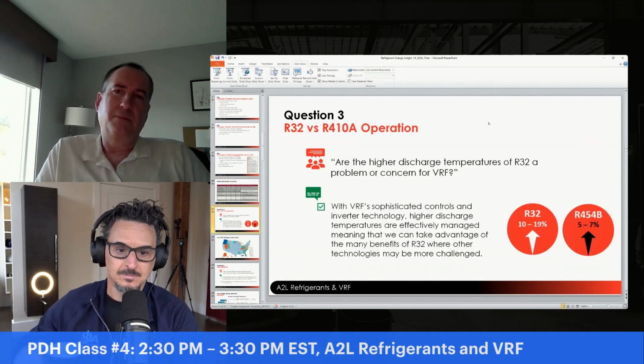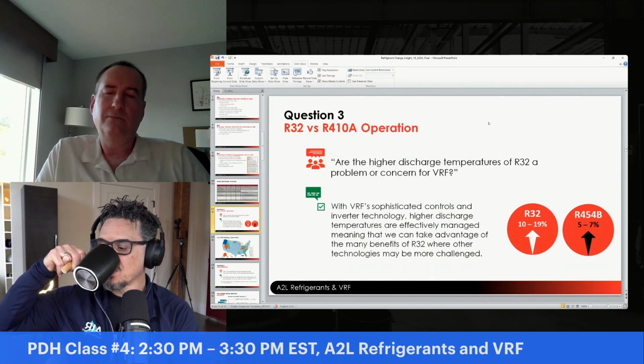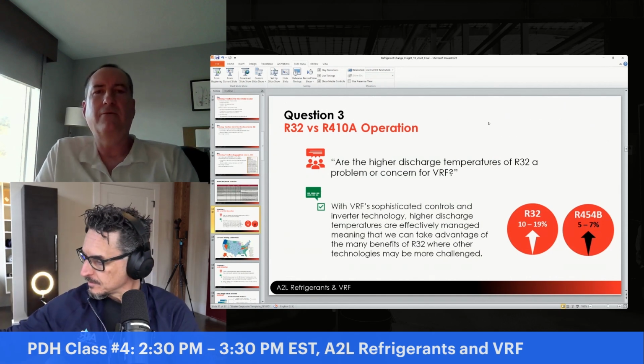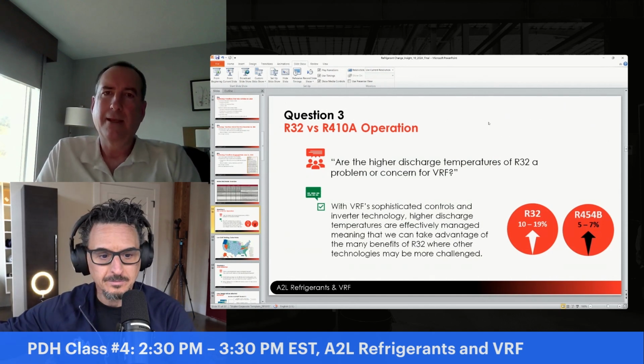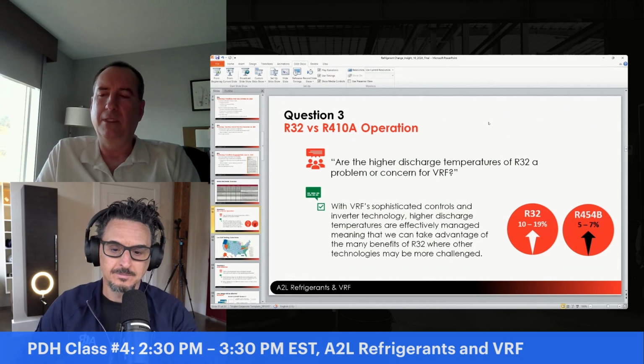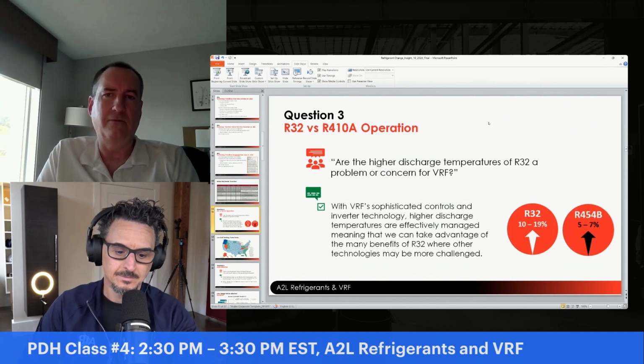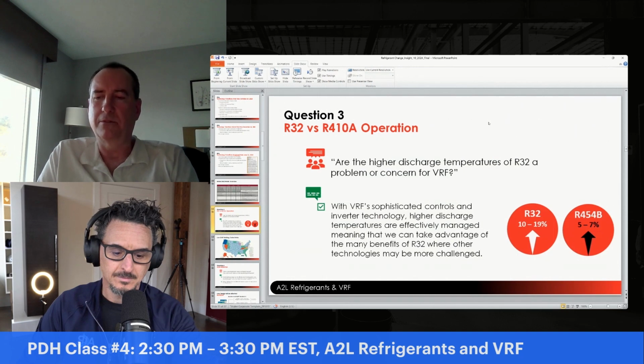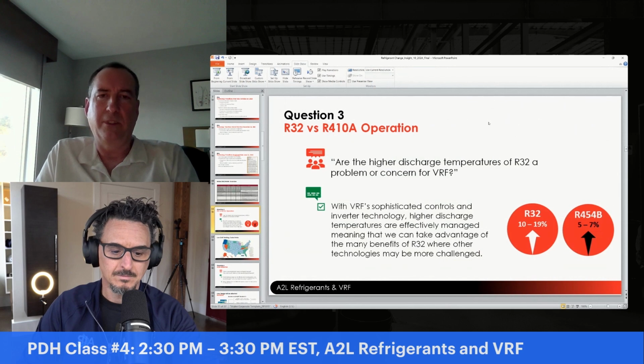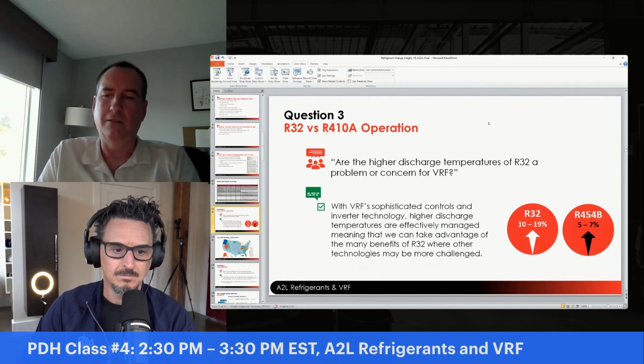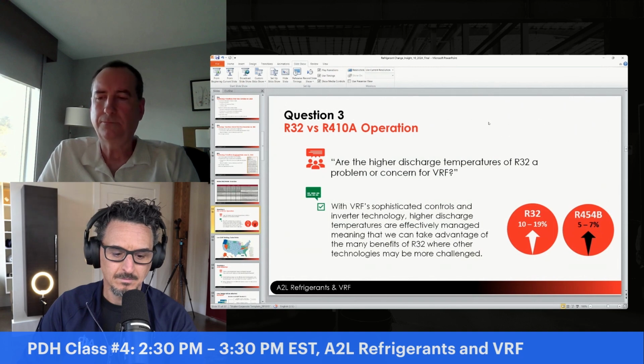So here's one of the differences between these two refrigerants: R32 does have higher discharge temperatures, and for some people that may be a problem, but for us it's really not. With our controls and inverter technology, we can manage these slightly higher temperatures without any problem. Doing that means we can take advantage of all these other benefits of R32, where other technologies may actually be a little challenged.